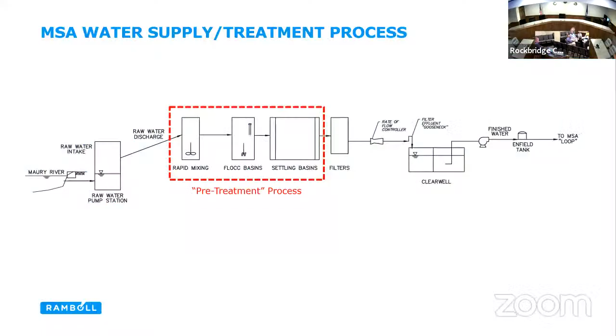For the water plant, conclusions: the existing water treatment processes are producing high quality finished water, but most of that equipment dates back to 1975, so significant investment decisions need to be made. That pre-treatment structure is in very poor condition—continued repairs and rehab are not cost effective or sustainable. We also need to fix the hydraulic bottleneck that's reducing the actual operating capacity of the plant down to the 3.5 MGD range. Additional deficiencies include the process equipment, issues with solids handling on the lagoons or sludge drying bed, and it's worth investigating standby power to provide complete backup power at the plant instead of just a quarter of its capacity. There are also improvements needed to the HVAC system on the 3rd floor, and to the instrumentation and SCADA systems.